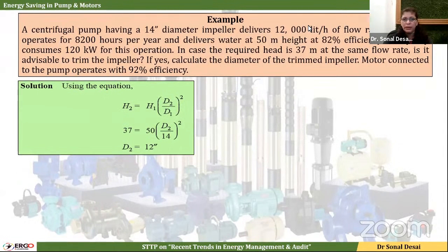A centrifugal pump has a 14-inch initial impeller diameter. It was delivering 12,000 liters per hour of flow rate, operating 8200 hours per year, delivering 50 meters of head at 82% efficiency, consuming 120 kilowatts. Now the requirement is 37 meters of head at the same flow rate. So we don't need to change the flow rate, but we need to reduce the head.